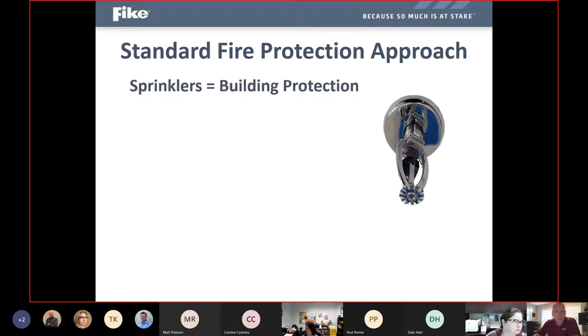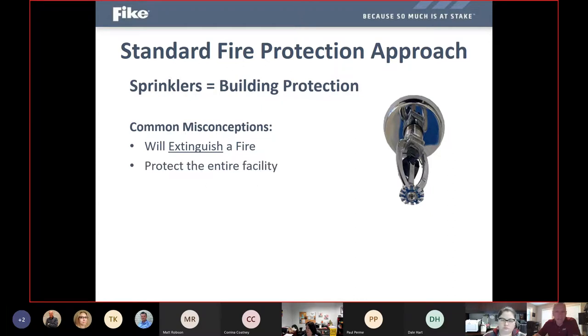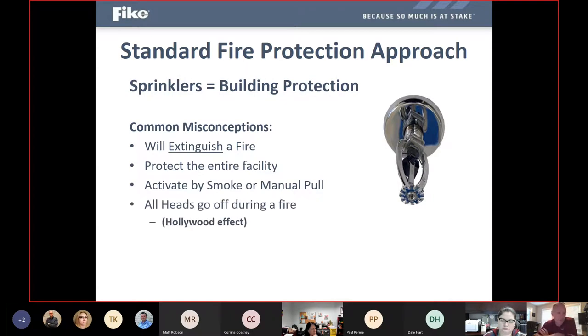The standard fire protection approach that everyone's obviously very familiar with are sprinkler systems. And sprinklers are great for building protection, but there's a bunch of misconceptions associated with sprinkler systems. For example, many folks think that sprinklers will actually extinguish a fire, that they'll protect the entire facility, that you can set a sprinkler system off by activating a manual pull station or a smoke detector going off, and also that all of the heads go off during a fire, which is what we refer to as the Hollywood effect. You know, in several movies and TV shows, somebody holds a lighter up to a sprinkler head, and all of a sudden, every sprinkler in the hallway and the building and the room starts spraying water everywhere. That's just not how sprinklers are designed to work.